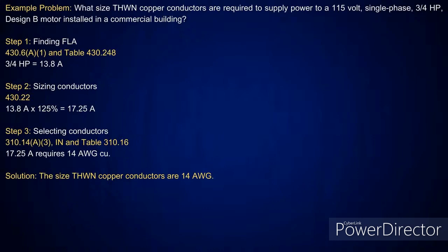So in this case, for that 3/4 horsepower single phase 115 volt motor in table 430.248, it's going to tell you it's good for 13.8 amps. And then I go to step 2, and you go look at 430.22, and where I have a single motor there, you have to take it at 125%. Now, if I have multiple motors here, you take the largest motor at 125%, and all the rest of the motors are at 100%. Now, for this one, 13.8 amps times 125% gives me 17.25 amps. The next size above that for table 310.16 in the 75-degree C column is a number 14 conductor.